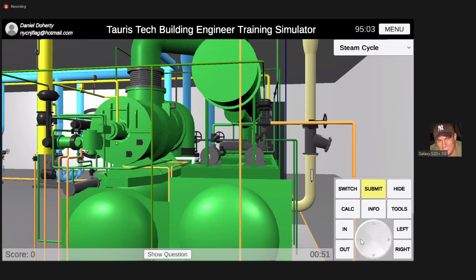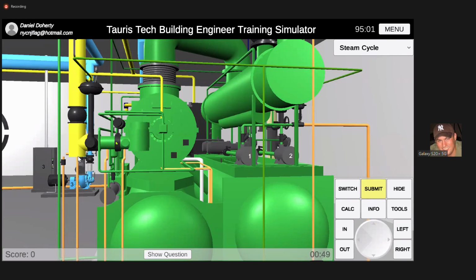Look at your blowdowns, look at your drip legs. Condensate wouldn't come out up here because condensate is heavier than steam, so water is always going to go to your lowest point. That's why this line is here, that's why this line is here, that's why this line is here. Condensate is always going to be on the bottom no matter where you are.